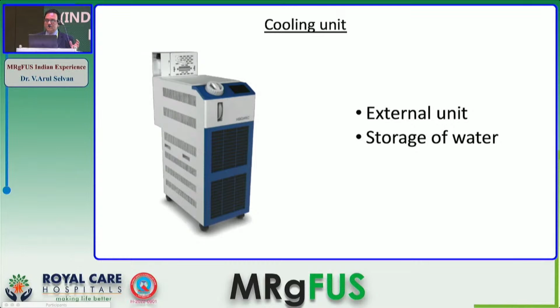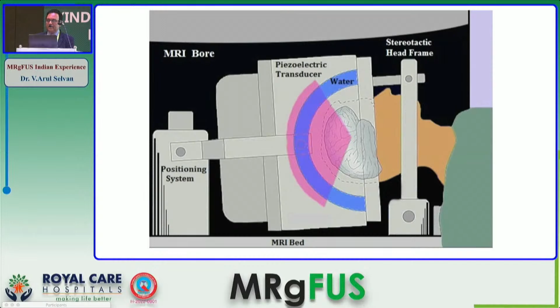This is the whole MRI bore, the positioning system which is in the MRI room. The water system is a little bit away, and the water circulates around the head in a silicone membrane with the piezoelectric transducer, along with a stereotactic head frame to prevent movement artifact by the patient. This is the sonic elements display, so you can see how many are active.